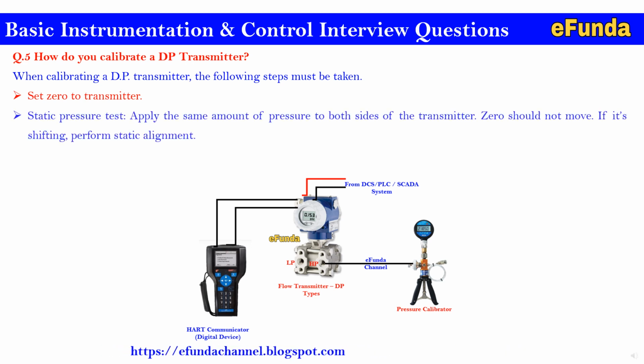Second, static pressure test. Apply the same amount of pressure to both sides of the transmitter. Zero should not move. If it is shifting, perform static alignment. Here in this setup, we have kept the LP side open and HP is connected to the pressure calibrator, so as to see whether we are getting the differentials or not. And once you confirm the differentials are coming, then you can do this test as well.